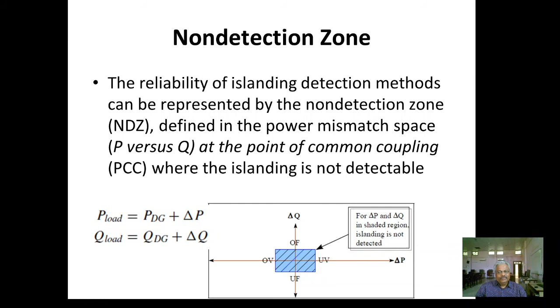The reliability of islanding detection methods can be represented by the non-detection zone defined in the power mismatch space. This is the power mismatch space at the point of PCC where islanding is not detectable, because the delta P and delta Q values are in this range. We are defining over frequency, under frequency as 49, 51, and voltage 0.9. In this range, if there is power either fed to the utility or taken from the utility, the delta P value is very small, and you will not be able to detect the opening of a circuit breaker, and it is not a good situation.